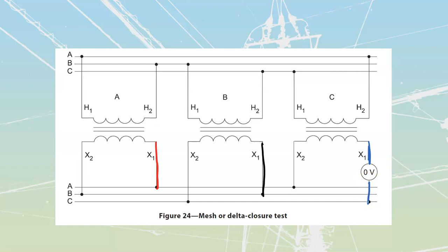These are the correct connections as far as we're concerned. If I look at my lines, I see no more than two connections per line. But the very last thing I'm going to do is close in with a closure test. The closure test is theoretically supposed to read a value of 0 volts.